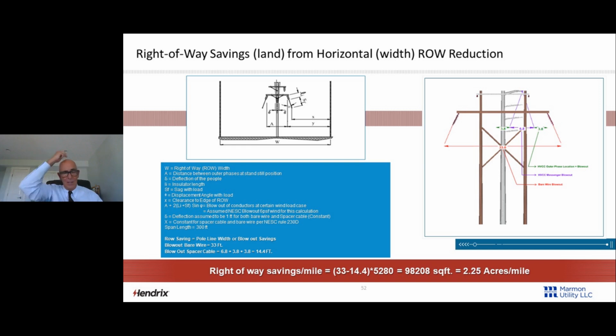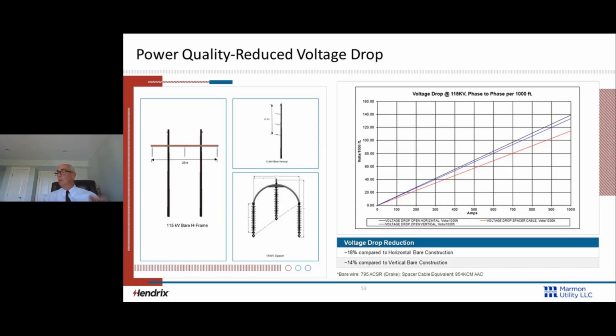We've got to do these calculations for the blowout because my right of way includes the blowout. There's the formulas. Basically, it tells us that we're saving so much on the width, and we're saving 2.25 acres per mile when we're building spacer cable versus bare wire for this case. The 2.25 acres per mile, does that mean anything to you? Does that mean anything to your regulators, to your permitting, to the project, to your trimming? Anyway, I'll leave that to you.